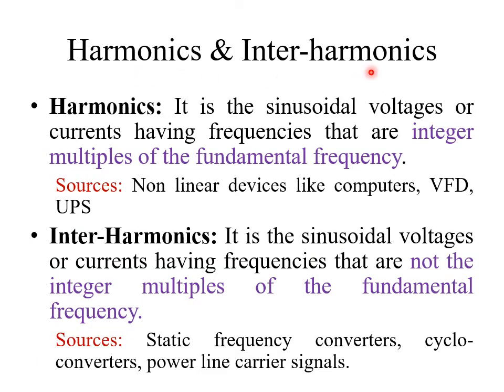Harmonics are defined as voltages or currents whose frequencies are integral multiples of the fundamental frequency. For example, if the fundamental frequency is 50 Hz, the harmonics are 100 Hz, 150 Hz, 200 Hz, and so on. Sources of harmonics include non-linear devices like computers, variable frequency drives, and UPS systems that use power electronic components such as SCR, IGBT, and MOSFET.